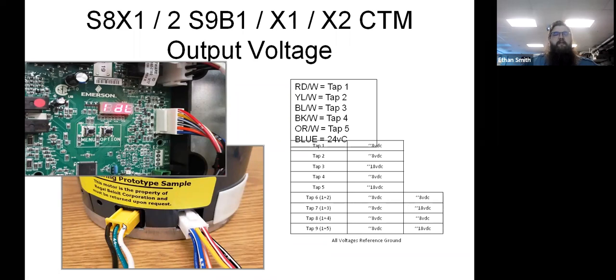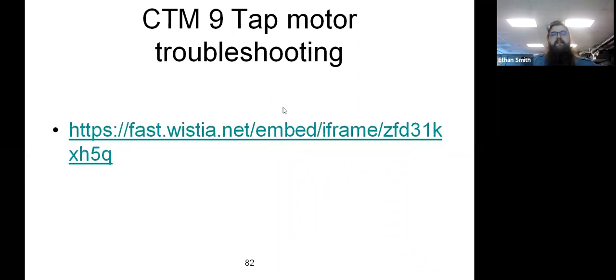You may just have 2 separate plugs, a high voltage and a low voltage plug, but the tests are the same, guys. Check for high voltage, check for low voltage. If you got both of them, motor doesn't run, dead motor. Okay. If you're not getting low voltage, but you're getting high voltage, when you should be getting low voltage, then we need to look at the wiring or the control board. But they're pretty simple, guys. Either it works or it doesn't when you give it the right inputs.